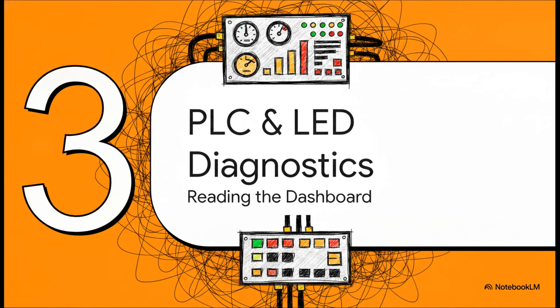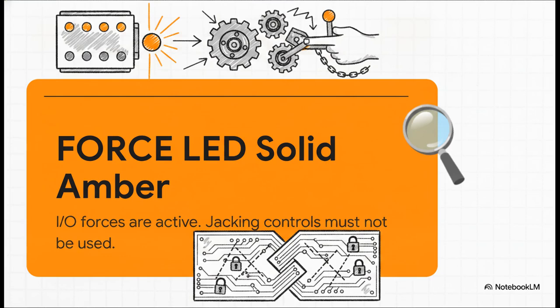Moving right along to Section 3, PLC and LED diagnostics. Let's talk about reading the dashboard. Look, if there is only one single thing you remember from this whole explainer, let it be this exact definition. A solid amber force light on your PLC means overrides are active. This means someone, probably during some prior maintenance or troubleshooting, has forced inputs or outputs in the programming. They've intentionally bypassed the natural safety logic of the controller.